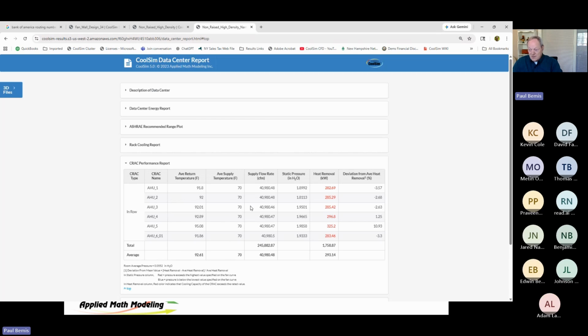You can use low temperature as a way to get away from compliance problems if you drive temperature low enough, but it's going to be expensive to do that. And you may want to do that in a case where you're in N+1 state because something has failed, or N+2, get the temperatures down a little bit.